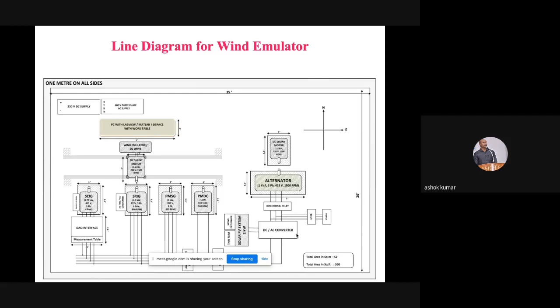If you design a generator, we can characterize it in our emulator lab - how it responds at minimum and maximum speed, and under unbalanced load conditions. We used an alternator as the grid, varied its speed, created unbalanced situations, and implemented physical faults to check how the generator, solar PV system, and converter respond. This is one of the smart grid systems we developed in our lab.